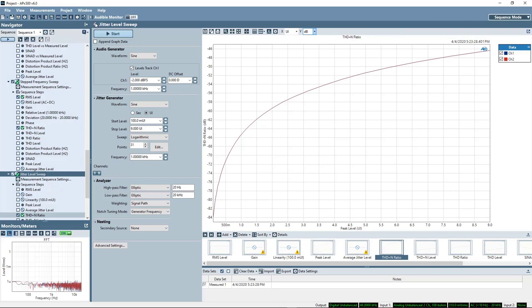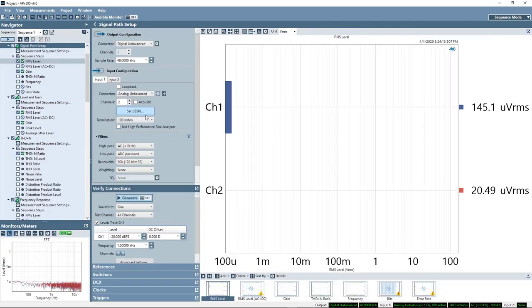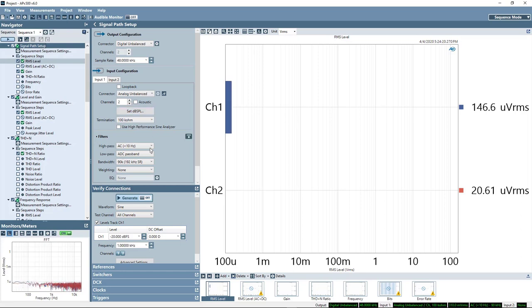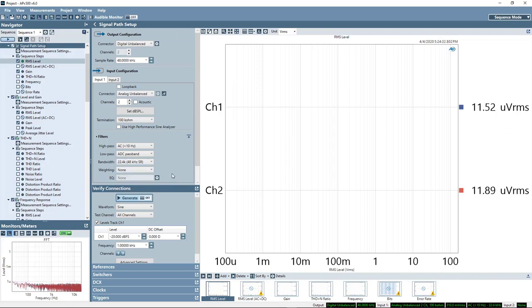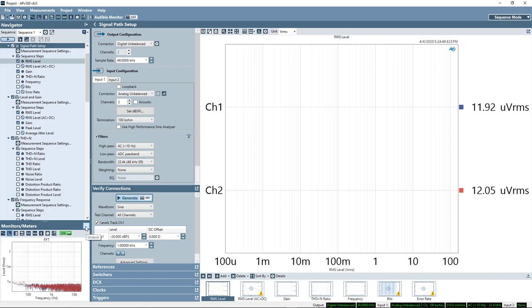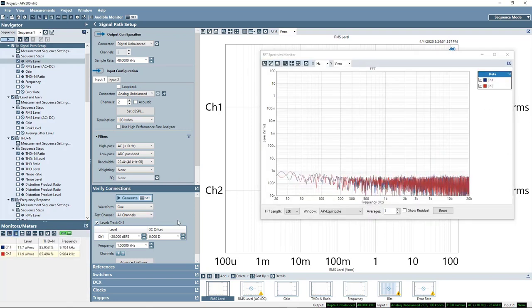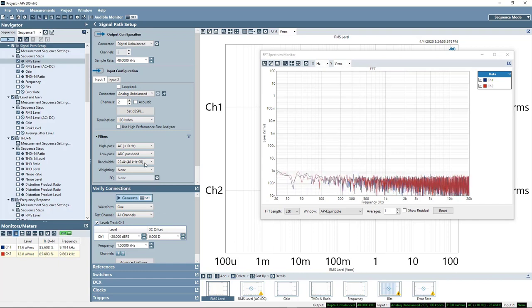Now when I started out, I skipped over a couple of settings that are interesting to look at in the input configuration. So the first is the input bandwidth. Now, if we're only going to test a device in a 20 kHz bandwidth, it's very convenient to just set this to 22.4 kHz bandwidth. That's running the internal ADCs of the APX itself at 48 kHz sample rate. And that really will just make the software faster and save us from processing data that we're not interested in.